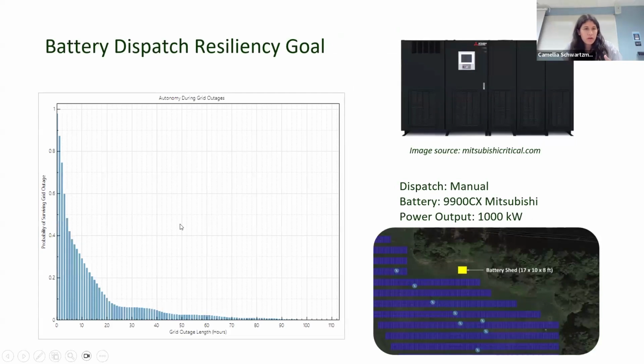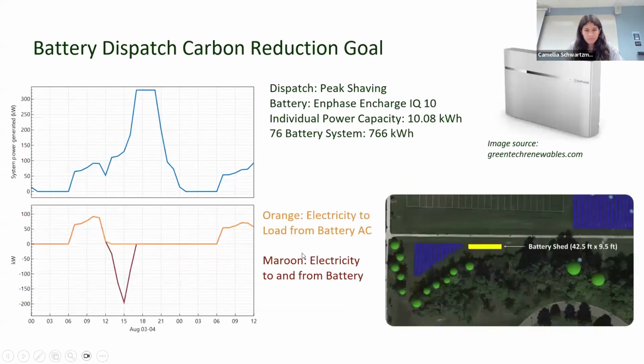So for this battery dispatch for the resiliency goal, we used a 9900CX Mitsubishi battery with a power output of about 1,000 kilowatts. Using the SAM simulations, we can see that the probability of surviving a grid outage, the autonomy of surviving a grid outage, is about 84% probable. So it's not 100%, which is what our goal was, but it is likely to survive a 2-hour grid outage with this battery system. And the battery shed is located on the top right of the geothermal plant, which you can see in the bottom right.